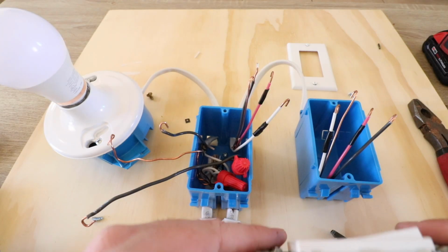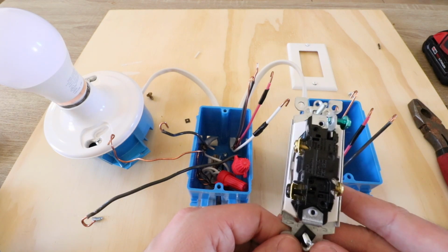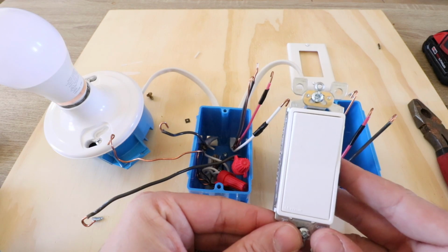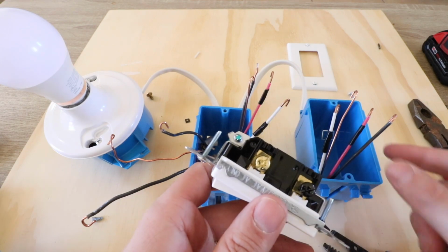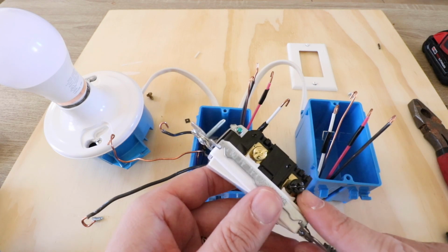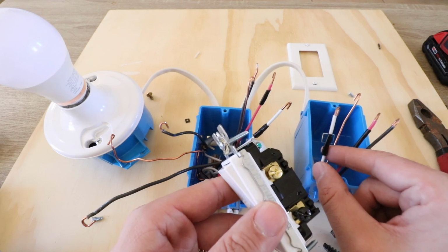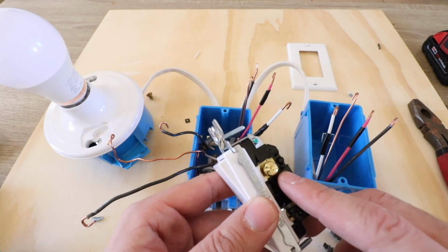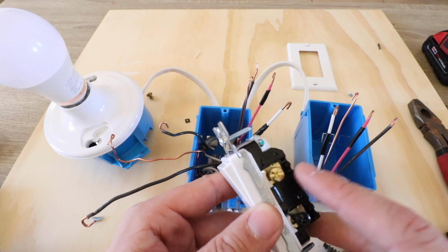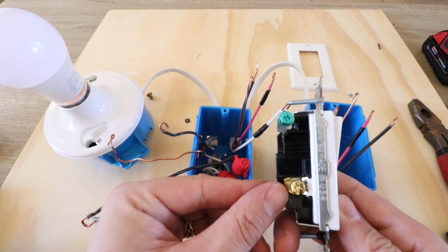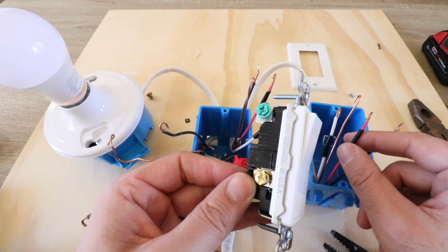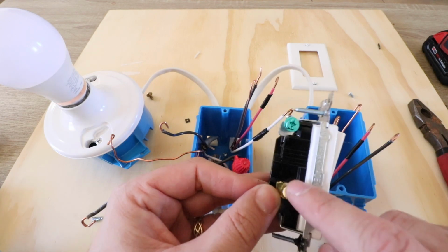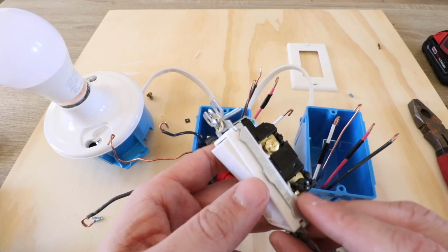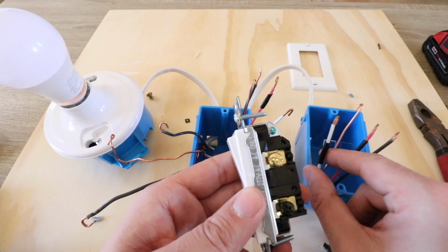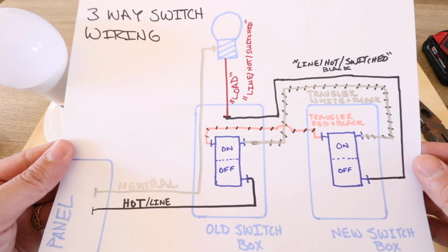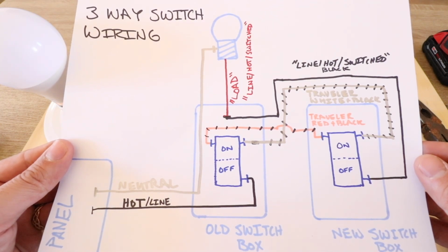Now that we've got the wires marked, we're ready to wire up the three-way switch. We want to be consistent with each three-way switch and make sure we wire it up the same way. The black wire goes on the black terminal, and the white wire marked as a traveler goes on the terminal above that. I need to be consistent and do that for each three-way switch on the same side with the same terminals. On this side, I'm going to put the red wire that's marked as a traveler. So we'll have the red wire on its own on one side of each three-way switch, and on the other side, the black wire and the white wire marked as a traveler.